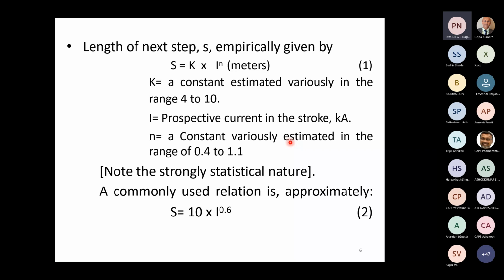S equal to K I to the power of N. Because of the statistical nature, it is possible that sometimes, at relatively rare times, there can be failure of the protection system. Now, commonly used values for the constants K and N are 10 and 0.6 respectively. So equation 1 becomes S equal to 10 times I to the power of 0.6. S is the next step length of the leader from the point P0. I is the prospective peak current in the stroke, and the constants are 10 and 0.6.